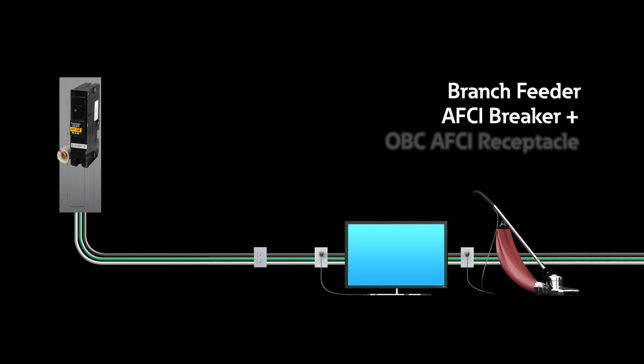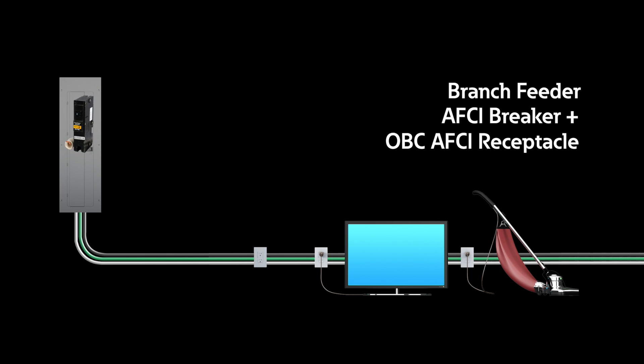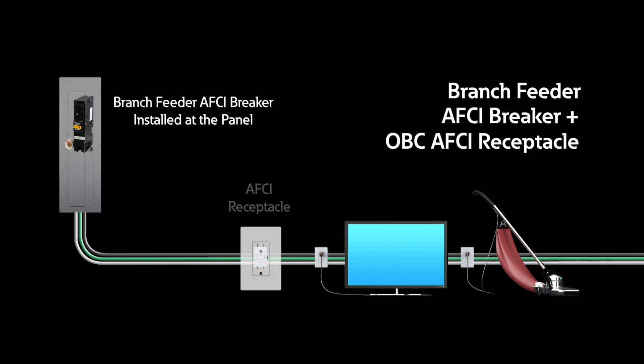Branch feeder AFCI breaker with outlet branch circuit AFCI receptacle. This is a branch feeder type AFCI breaker installed in the panel with an AFCI receptacle installed at the first outlet box on the branch circuit. This method protects the entire circuit from the source and allows local reset capabilities. However, it requires two AFCI devices that can be costly.